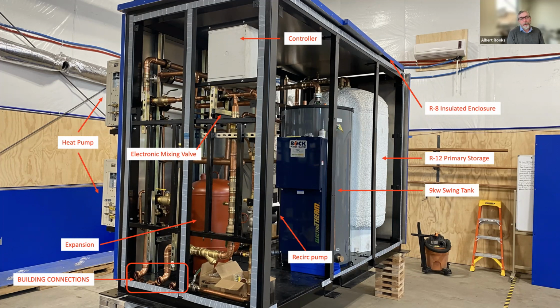I assume the tank skirt is welded directly to the tank frame and there's no thermal break in it. I think we're going to make a lot of heat in this thing. We're using this system as an educational piece, so we'll deploy an additional outdoor air temperature sensor, but actually put it in the enclosure, because I think in California we might make a little bit too much heat, and I might have to think about ventilating. I'm not real happy about that because I don't want to push the heat outside. I want to save it, put it in hot water, and keep going. So we'll find out what the conditions are.